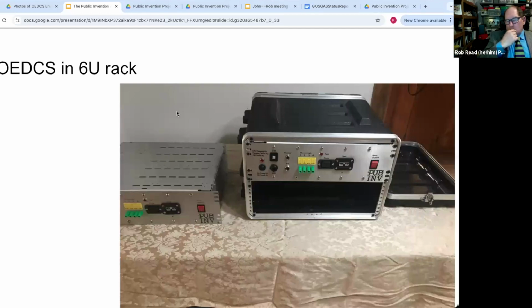And then the most recent work we've done is to make what we call the OEDCS, or the Oxygen Engine Digital Control System. So that black case is a 6U rack, and what you see there is the Public Invention control system, which controls an ion transport membrane, which makes pure oxygen out of normal air to be tanked for therapeutic purposes, or, since NASA's doing it, to fill spacesuits, or possibly on the surface of Mars to extract tiny amounts of oxygen from the Martian atmosphere to use as an oxidizer for a return trip from Mars, so that you don't have to take your fuel and oxidizer with you when you go to Mars.